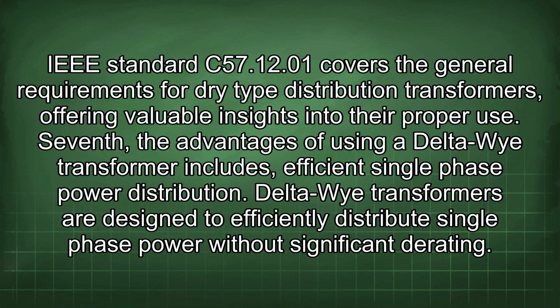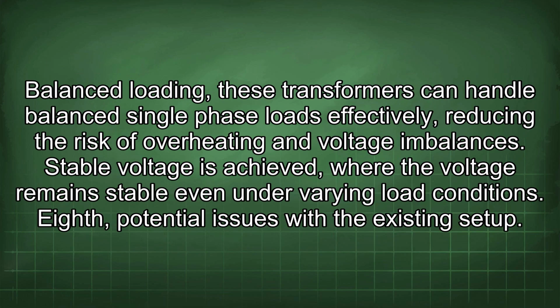Seventh, the advantages of using a Delta-Wye transformer include efficient single-phase power distribution. Delta-Wye transformers are designed to efficiently distribute single-phase power without significant derating. Balanced loading: these transformers can handle balanced single-phase loads effectively, reducing the risk of overheating and voltage imbalances. Stable voltage is achieved, where the voltage remains stable even under varying load conditions.